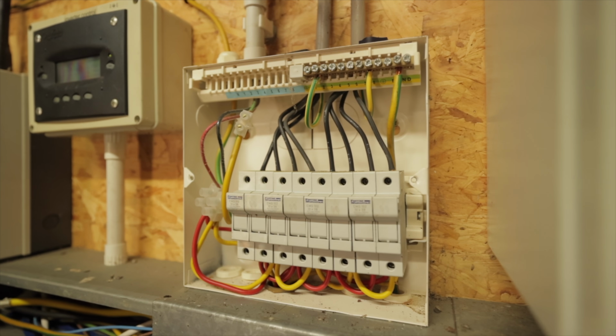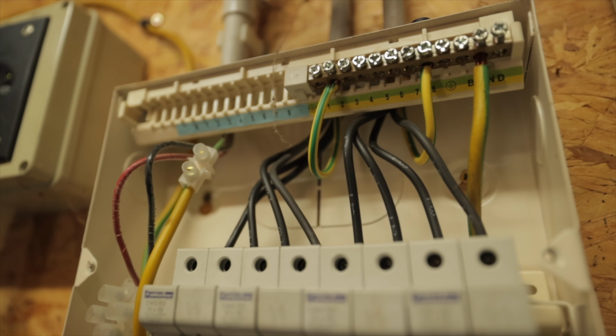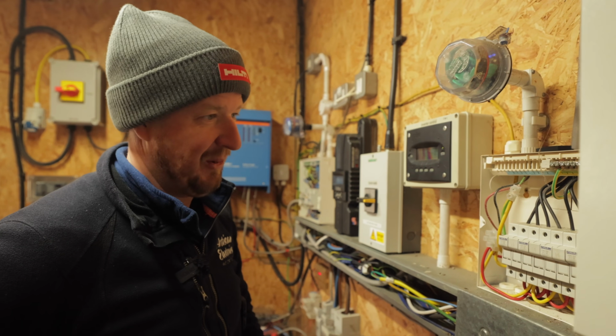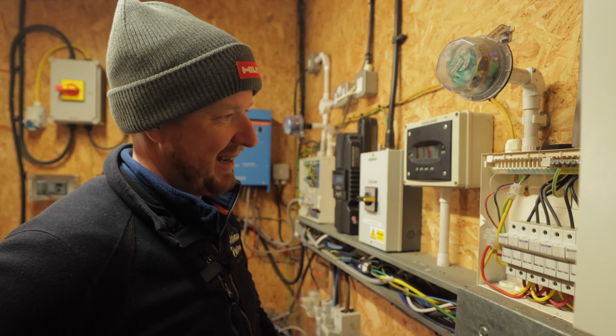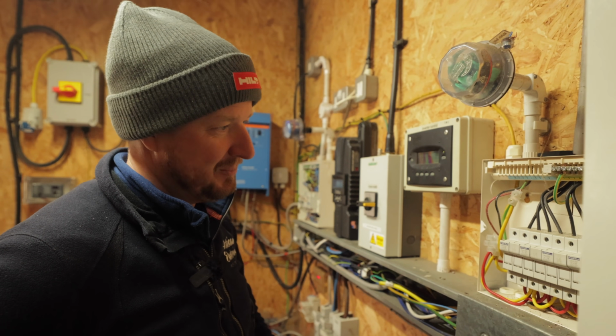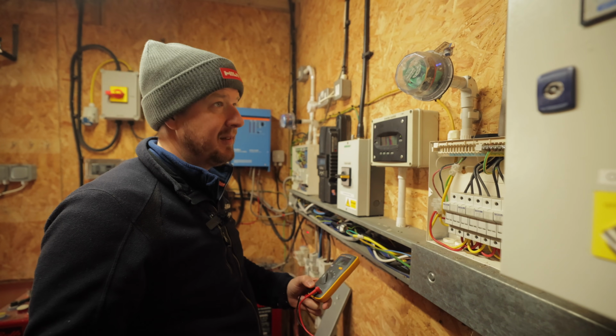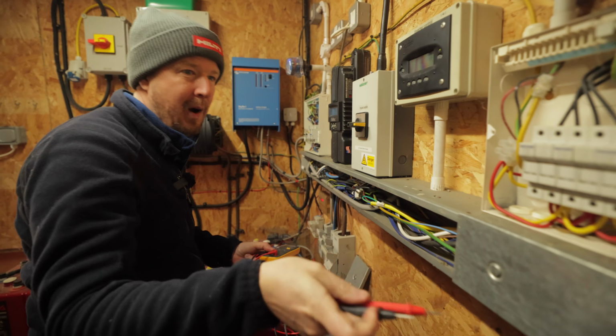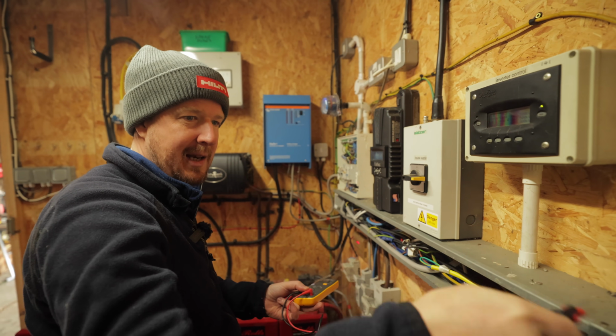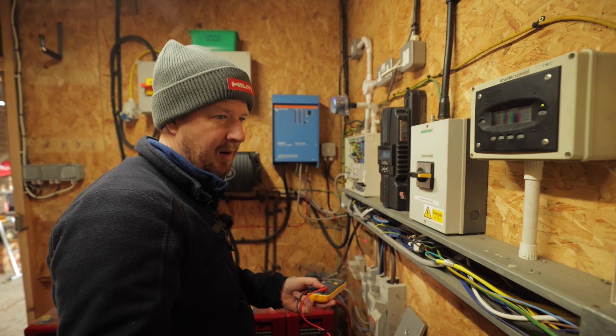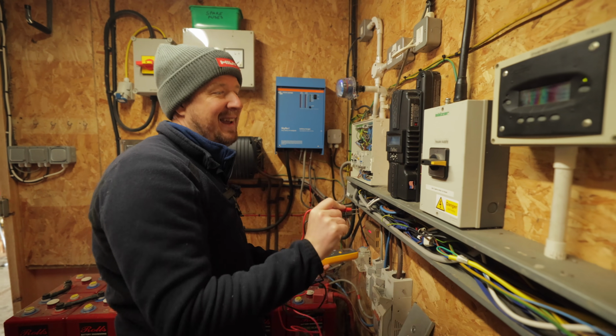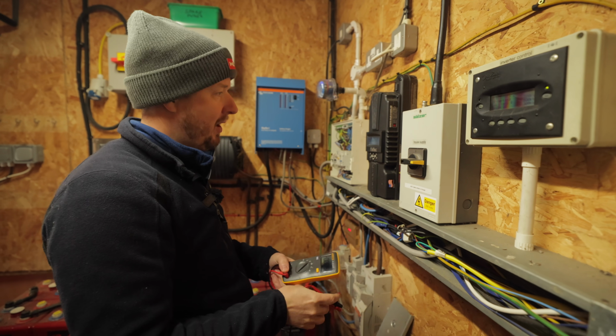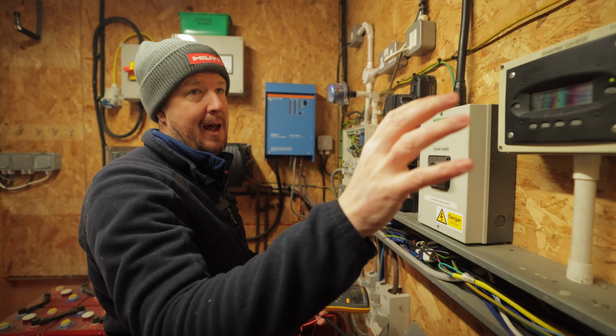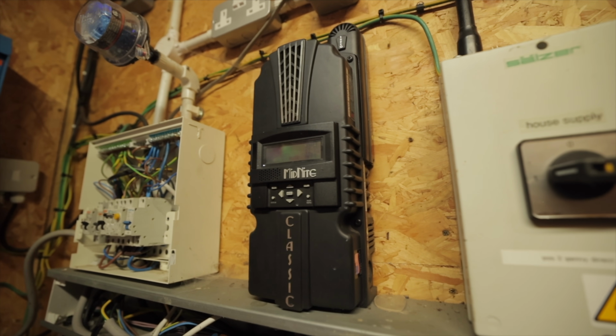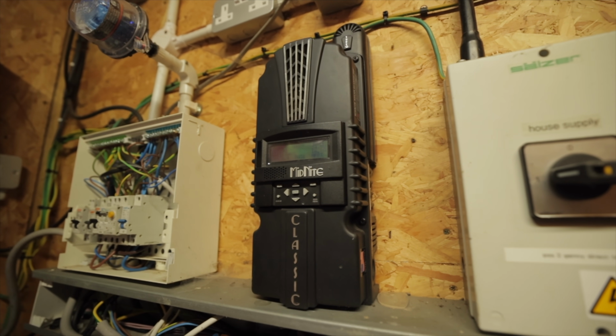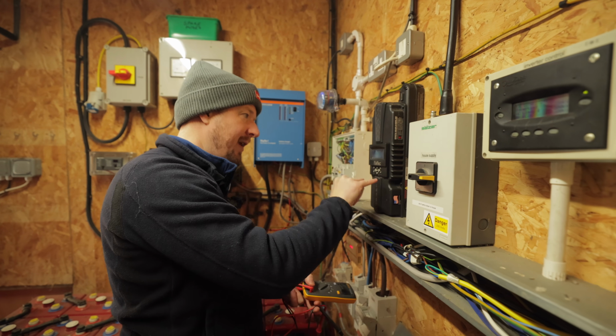It's just control flex they've used for the DC power, which is definitely not good. Those PV cables are not double insulated at all. They've made the effort to put a surge protection device in at least. They've wired it as almost like a ring, so they've looped in and out, and then come off the bus bar. But okay, this is where it gets clever. So the inverter is turning it from 110 volts, or 107 volts DC, to 24 volts.